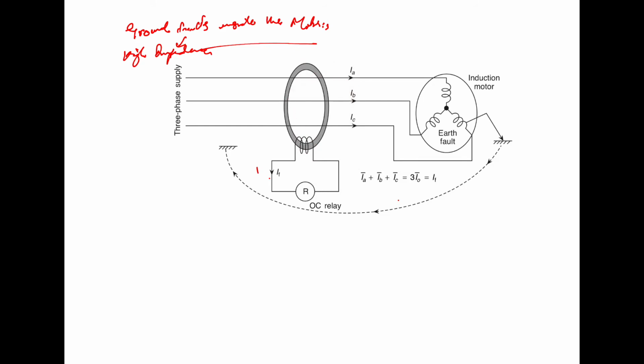Now, when the motor is running normally, the instantaneous sum of all the currents, IA plus IB plus IC, equals 0, so there is no net flux in the core and no voltage is induced in the pickup coil. Now consider the ground fault. The three line currents do not sum up to 0, and there is a net primary MMF proportional to the fault current returning to the supply neutral through the fault path. There is thus flux in the CT core because of that imbalance.